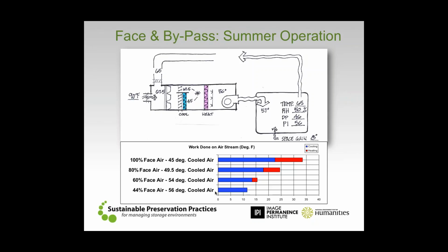These are a couple of options just to keep in mind. I know this example is very specific, but I always put it in there because I find a lot of situations where, once upon a time, at the initial design or installation of a mechanical system, the engineers were thinking ahead and saying, maybe we can achieve some energy savings by using a face and bypass operation. The face and bypass is basically where you don't send the full 100% quantity of the air over top of one of the coils. The face is the amount of air that goes over top of the cooling coil in this particular instance.